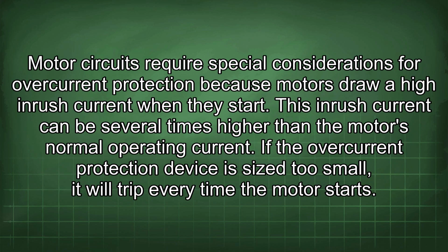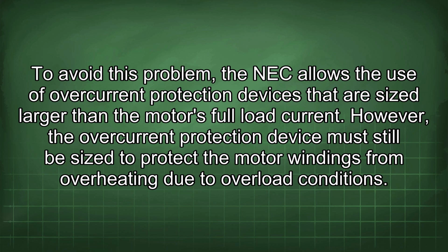Motor circuits require special considerations for overcurrent protection because motors draw a high inrush current when they start. This inrush current can be several times higher than the motor's normal operating current. If the overcurrent protection device is sized too small, it will trip every time the motor starts.